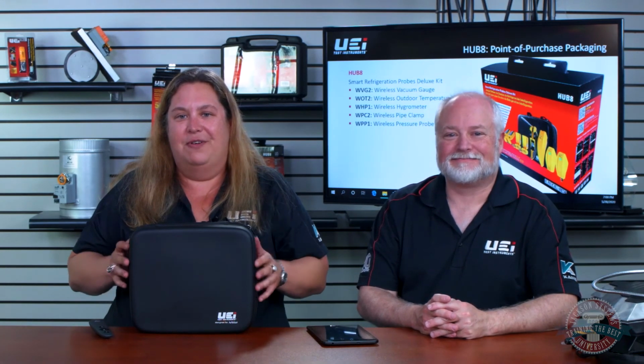Anytime we can speed up the jobs we're doing, it's going to be better for all parties involved. So it's the most complete kit available on the market. It's going to give you real-time target superheat calculations. It has the dual mode vacuum screen for the evacuation and rise test, and a 350 foot range. It's easy drag and drop, and you get everything in a kit. You might see the box, it's not so descriptive sitting on the shelf, but the box is going to tell you all that goodness I was able to explain.